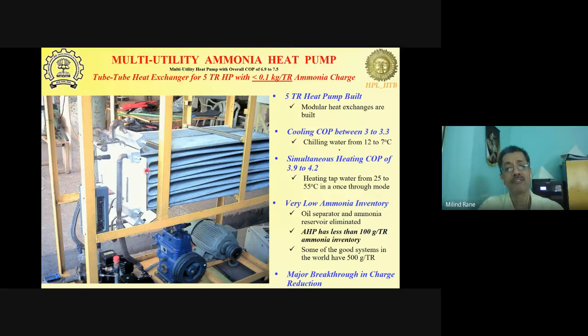So here is an example where we have deployed the tube-tube heat exchanger in a multi-utility ammonia heat pump, where on one side we are chilling water from 12 to 7, just like in any other chiller, and on the other side we are heating water from 25 to 55 in a single pass. No recirculation. Tap water can come in at 25 and get heated and go out at 55 in a single pass, no recirculation. Typically, most heat exchangers, whether shell and tube or plate type, are not in a position to heat water or any other fluid through such high temperature changes in a single pass.